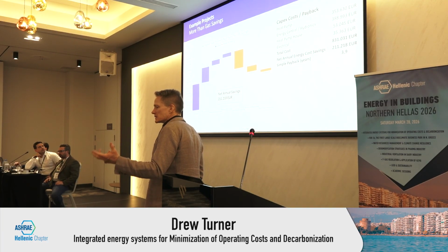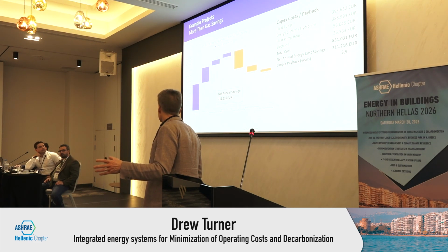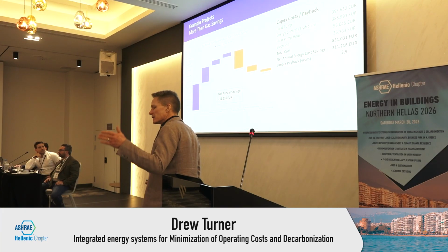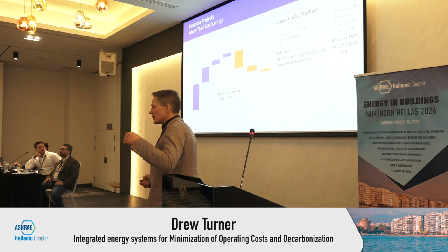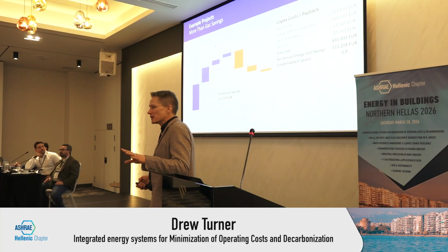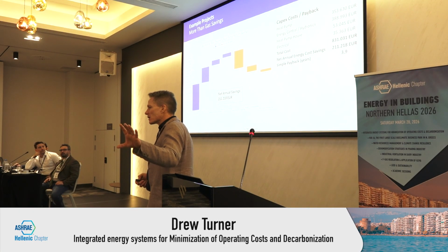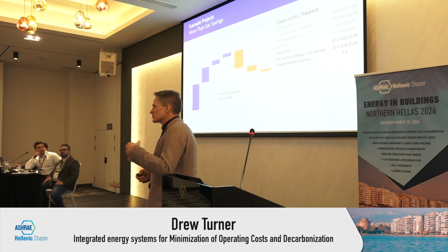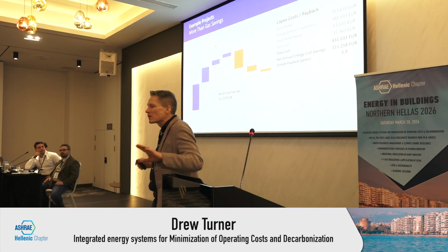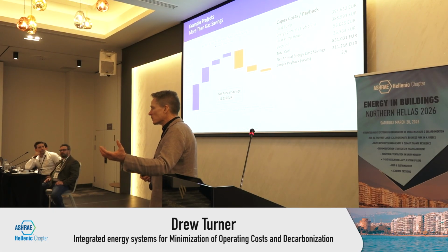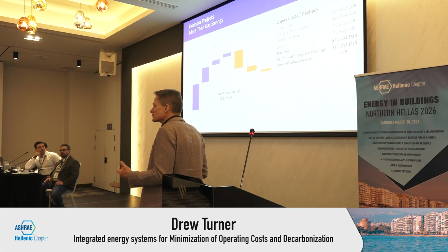the metal presses and welding lines of this manufacturing plant, then recovering the heat to replace the facility and process heat. This same manufacturing process is universal when you're making consumer goods: you have a parts treatment tank that all the parts run through before painting and assembly into the final product, if it's a metal part. You're heating it up to about 60 degrees C, which is a perfect target for recovery from cooling to replace the heat.